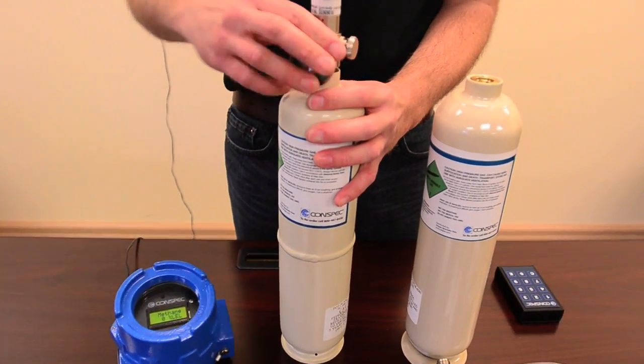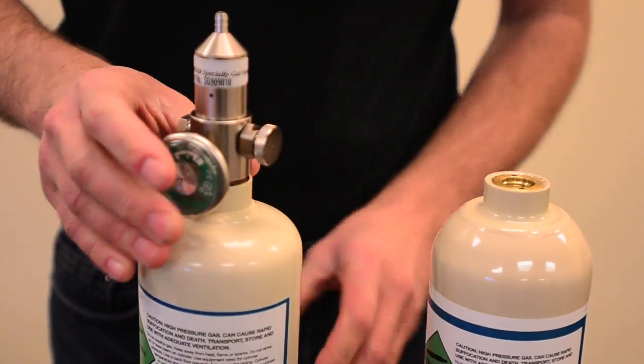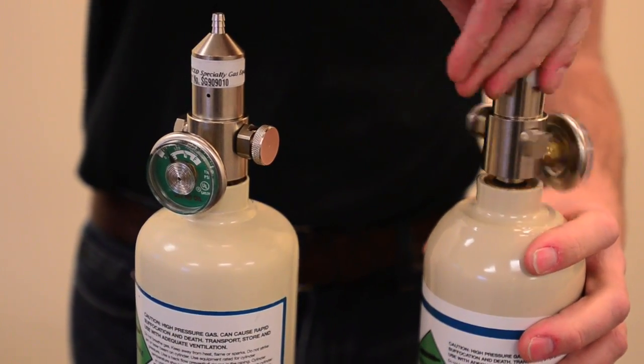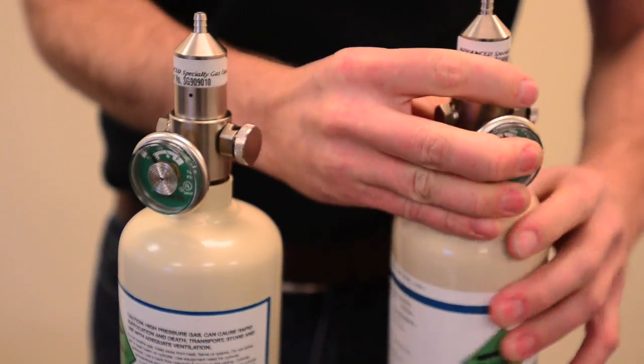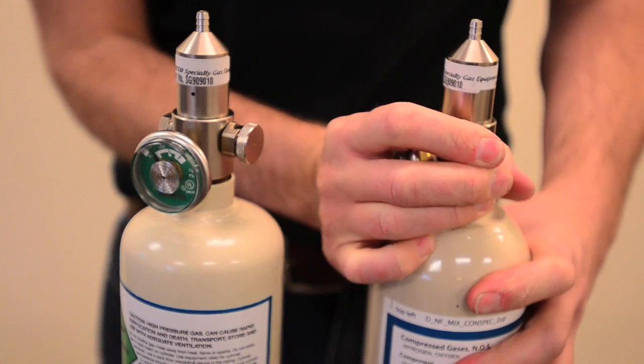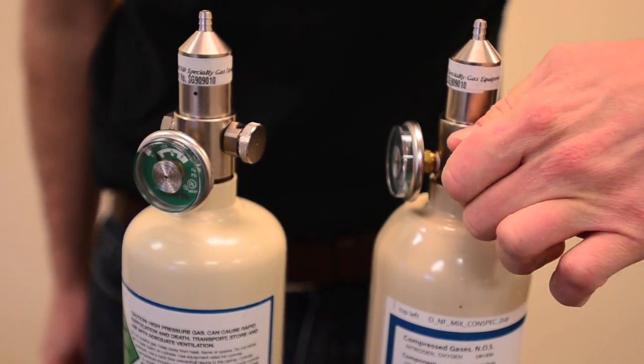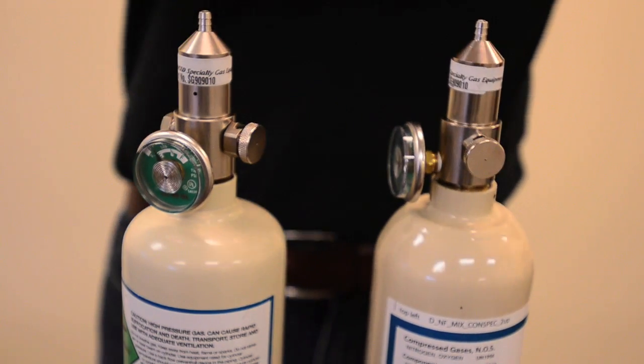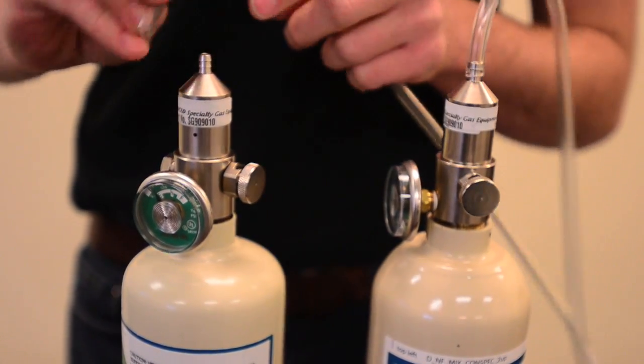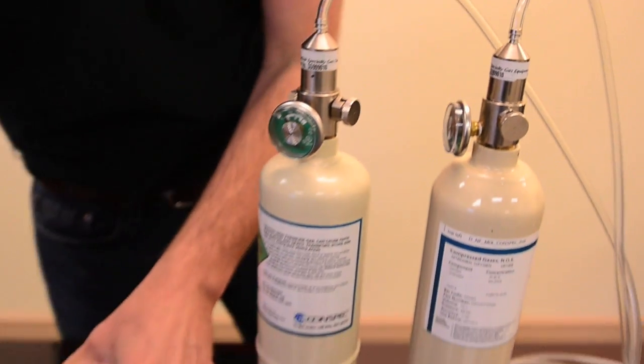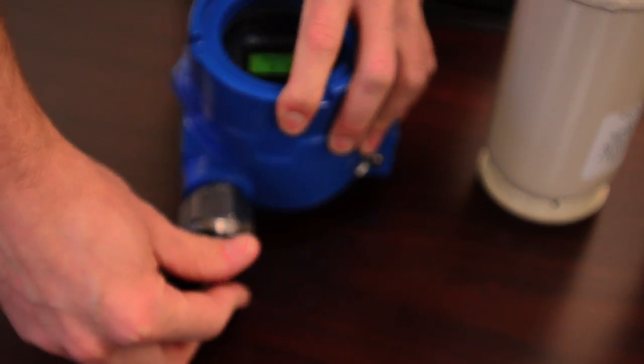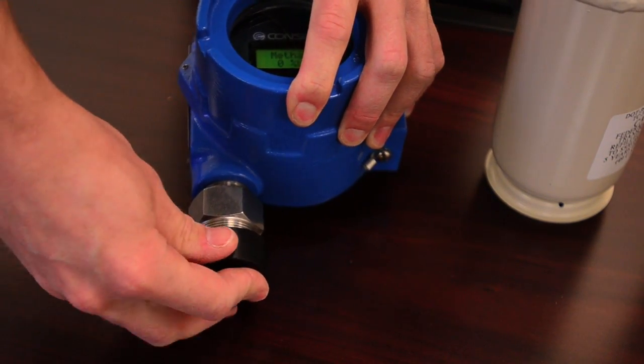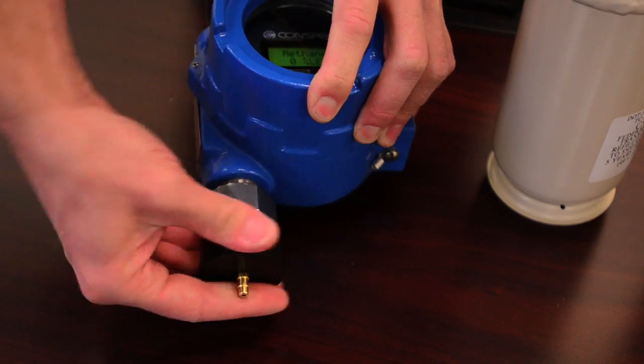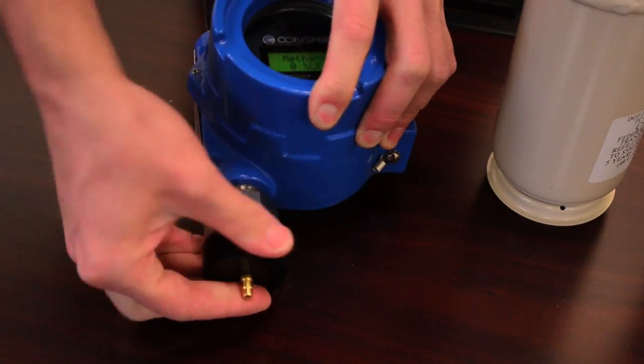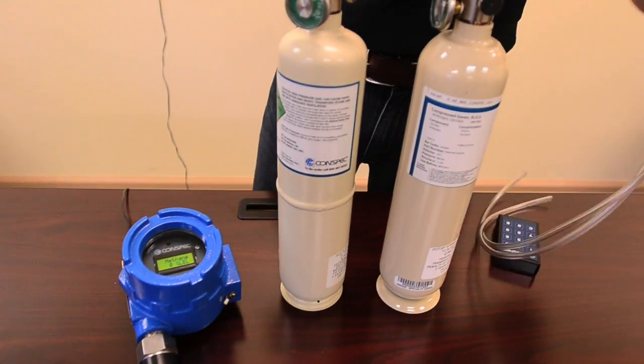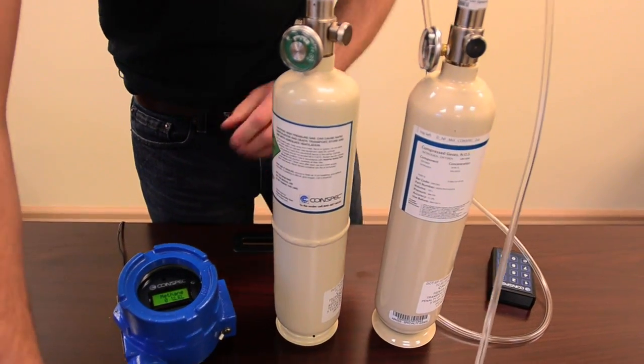So we want to thread on our flow regulators. These particular regulators have a thumb wheel to activate the gas. To do so, you want to depress the thumb wheel and rotate it 90 degrees, and then backwards, shut it back off. Connect our calibration tubing. It's a good practice, when you connect your calibration cup, to do that before you run the tubing over so that you don't unthread your tube barbing. And typically our monitors ask for zero gas first, so we can go ahead and connect our zero gas cylinder.